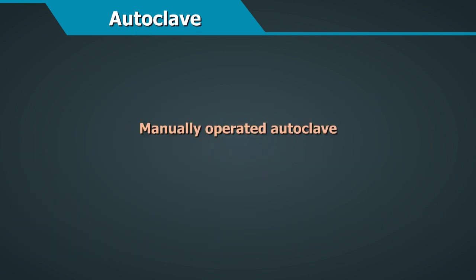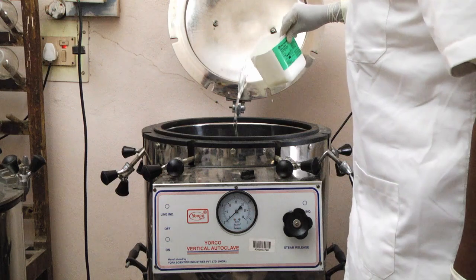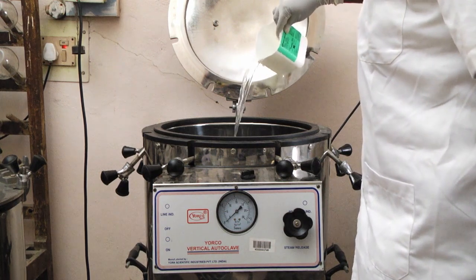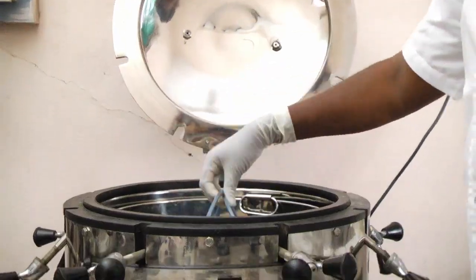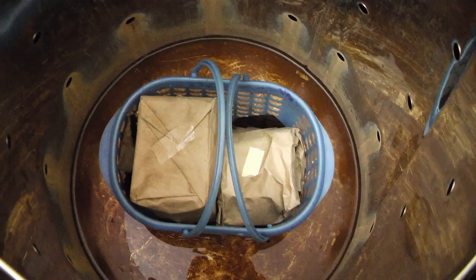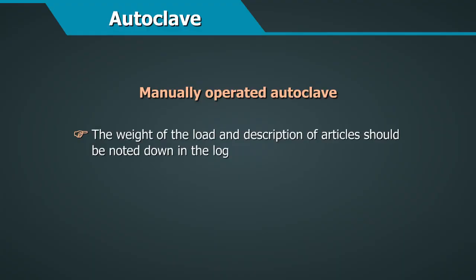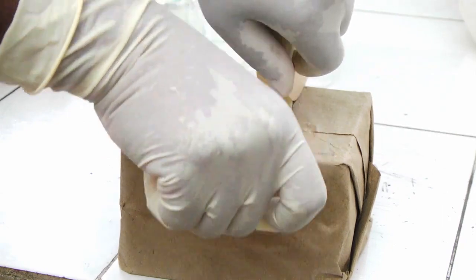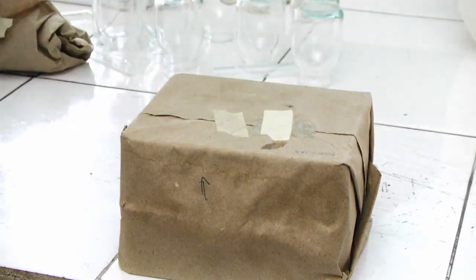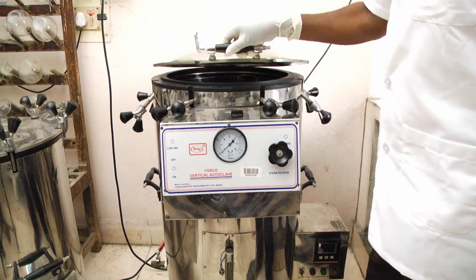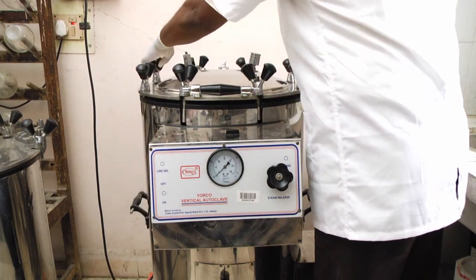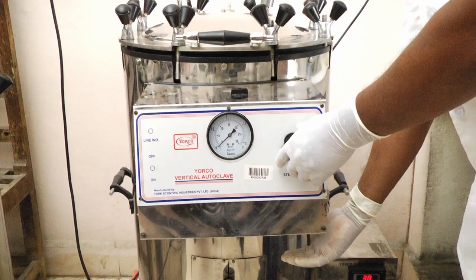Using a manually operated autoclave with thermometer and pressure gauge. Add the correct amount of water to the autoclave as directed in the manufacturer's user manual. When loading the autoclave, leave sufficient space between articles for the steam to circulate freely. Do not allow articles to touch the sides of the chamber or stand in water. Use a tray or wire stand in the bottom of the chamber. The weight of the load and description of articles should be noted down in the log. Place a control time steam temperature indicator strip in the center of the load where steam penetration is likely to be slowest. Secure the lid of the autoclave as instructed by the manufacturer. Open the air cock and close the draw-off cock.